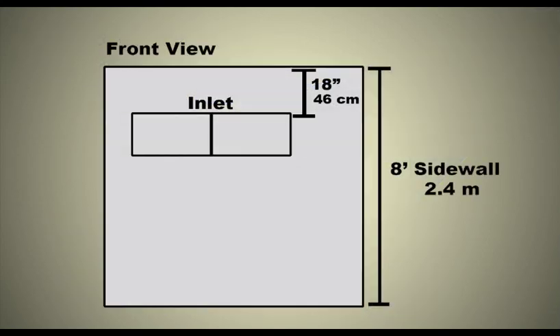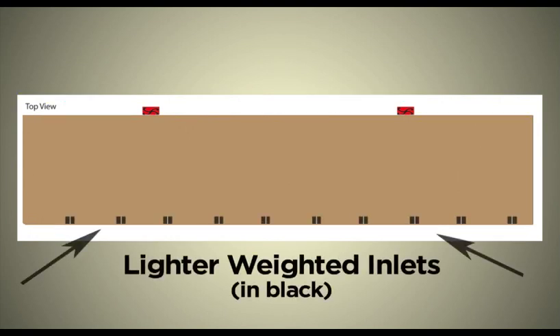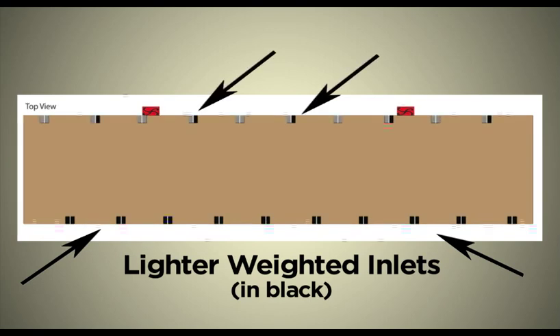Regarding placement: when possible, always install inlets down 18 inches or 46 centimeters from the top of the side wall. If minimum fans are on the side wall, the lighter weighted inlets are on the opposite wall from the fans. If there is not enough opening, place the remainder on the fan side.